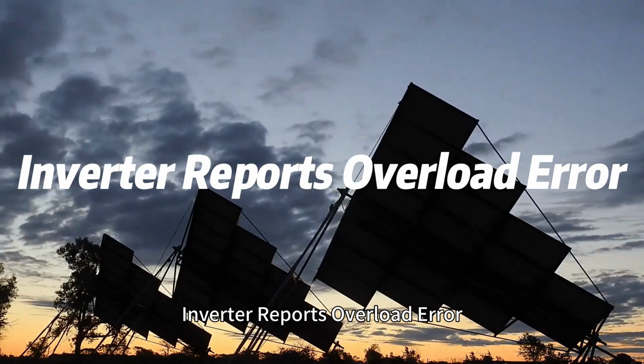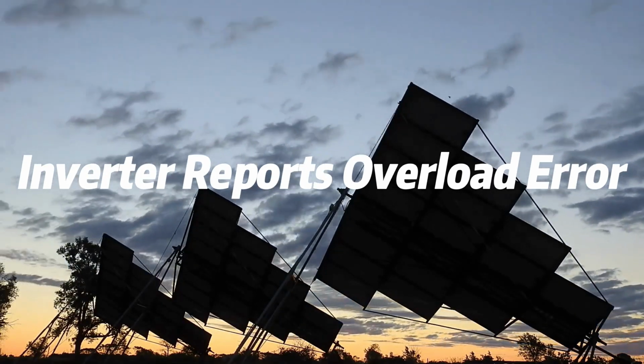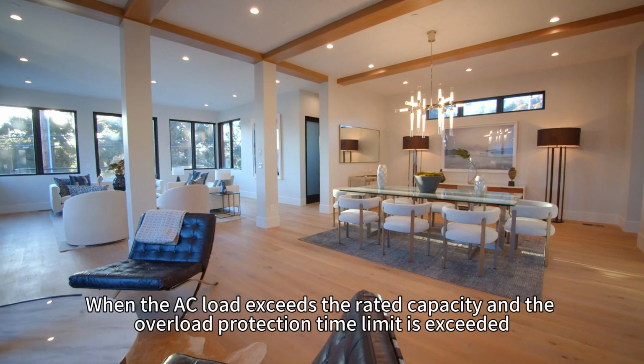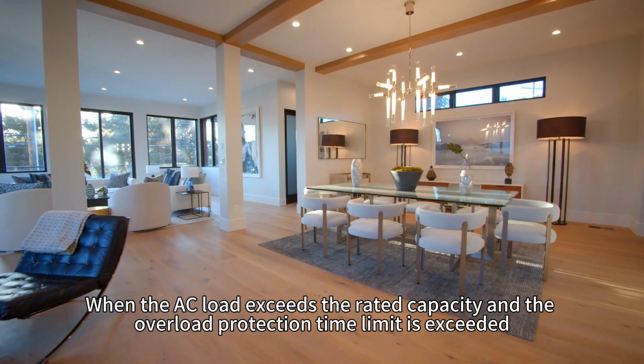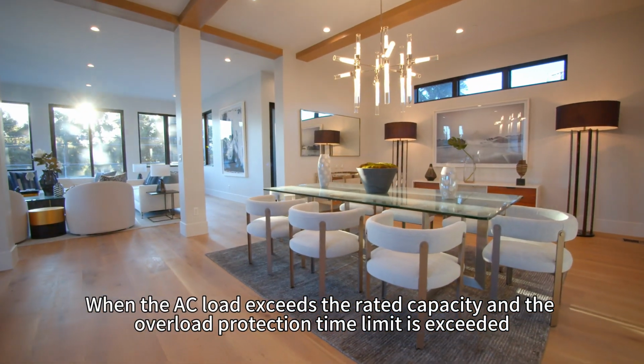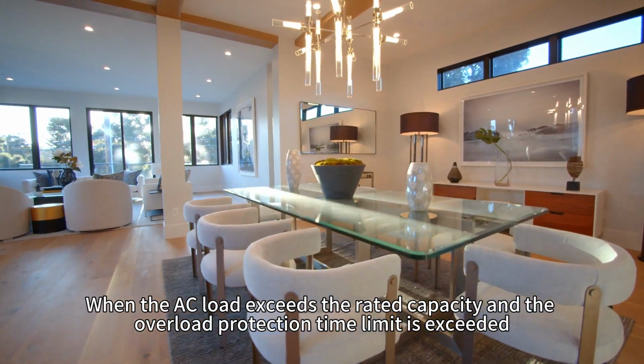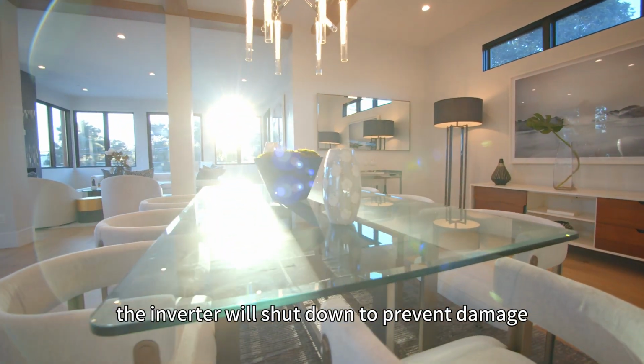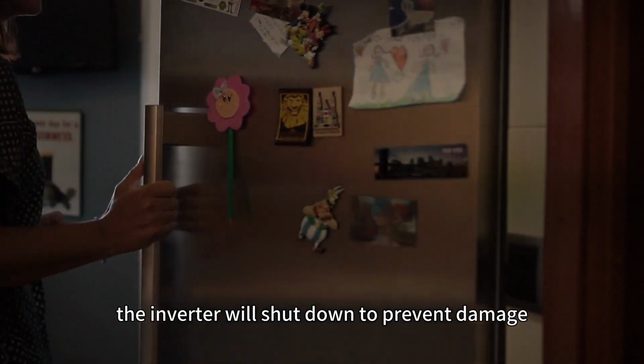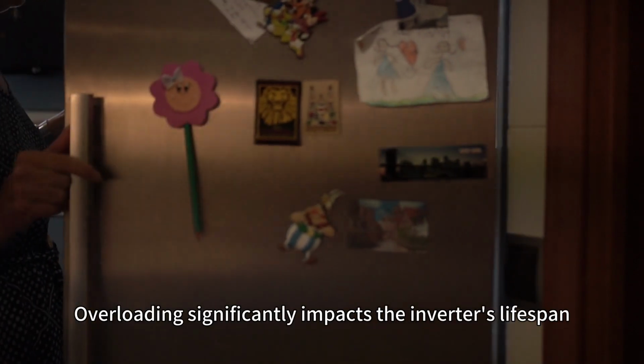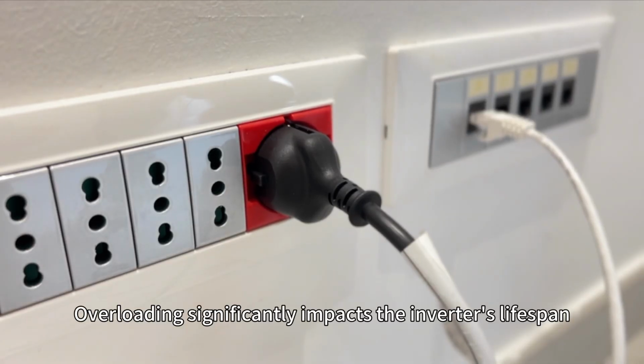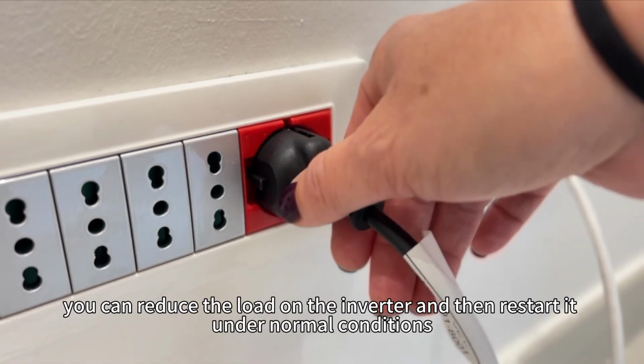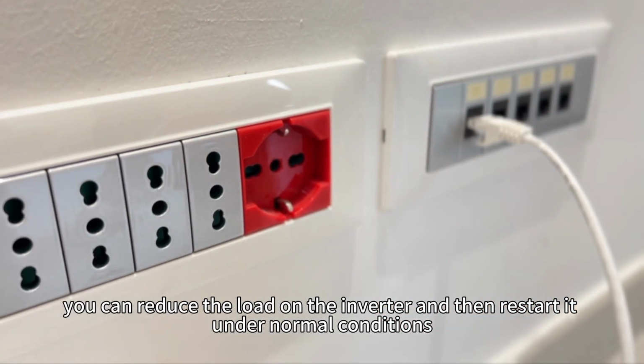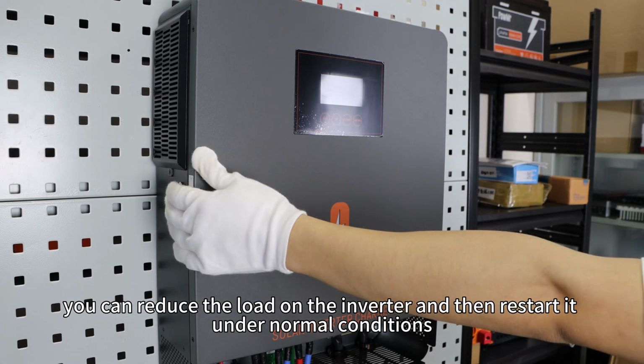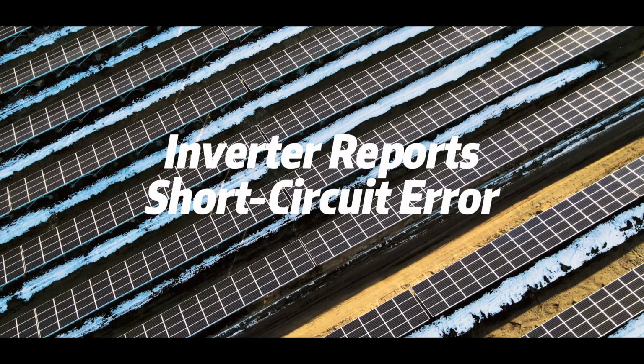Inverter reports overload error. When the AC load exceeds the rated capacity and the overload protection time limit is exceeded, the inverter will shut down to prevent damage. Overloading significantly impacts the inverter's lifespan. To address this, you can reduce the load on the inverter and then restart it under normal conditions.